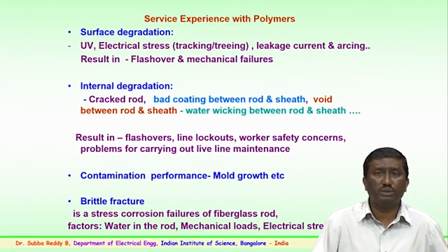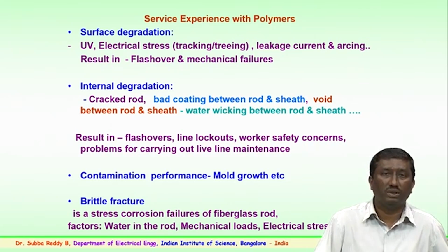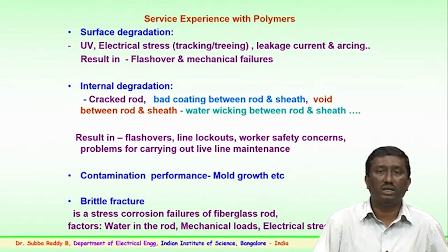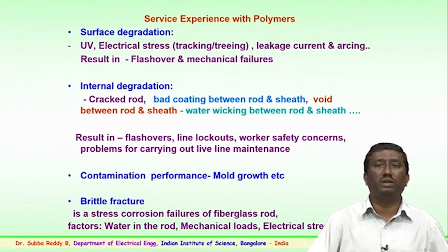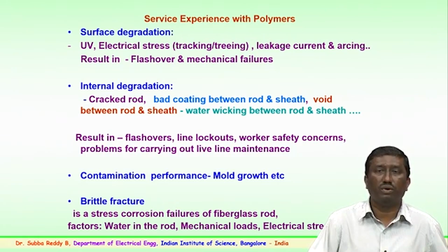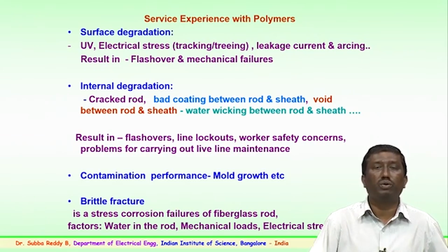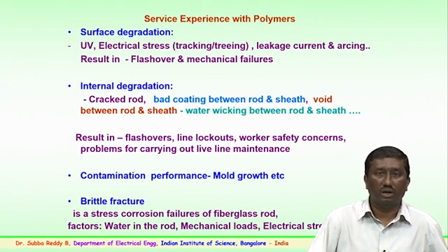So, service experience. What the utilities have is an earlier comparison, particularly of surface degradation, internal degradation, and so on. This service experience with the utilities is again from the initial technology which was adopted, as a first generation or a second generation. Now, the third generation, much improved insulators are available. So, earlier there were issues, there were some problems. Some, or most, of the problems are being overcome and a few of them do exist.